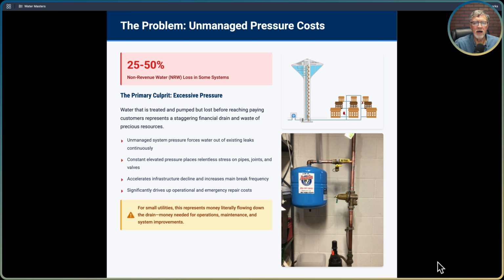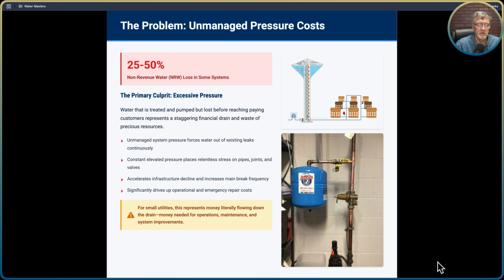All right. The problem with unmanaged pressure costs: there are a lot of small water systems that may have 25 up to 50% non-revenue water. This is a huge deal. One of the primary culprits is excessive pressure. Non-revenue water is water that's treated and pumped but lost before reaching paying customers, and it represents a big financial drain on your system and a waste of your resources. That's water you basically paid for that you're not getting any revenue for. So unmanaged system pressure forces water out of existing leaks continuously.